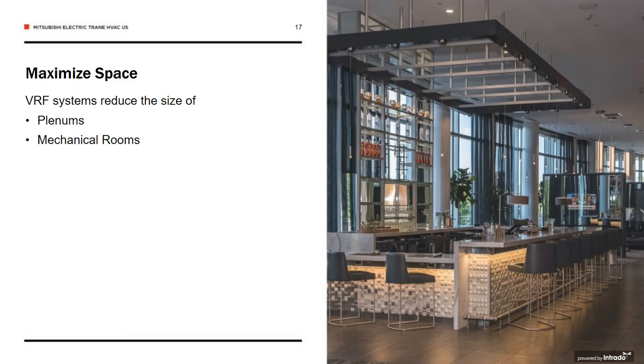An example of this is a speculative office that I worked on here in Dallas, Texas, where the developer was going from a 3-story to a 5-story application. In the 3-story, they used a rooftop VAV application, but they realized that to get to a 5-story building, they needed a different approach. And in comes VRF, and initially they were told it was too expensive, but we looked at ways that we could save on the floor-to-floor for their tilt wall, which led to savings of over $100,000 just by reducing that plenum height by 6 inches per floor.